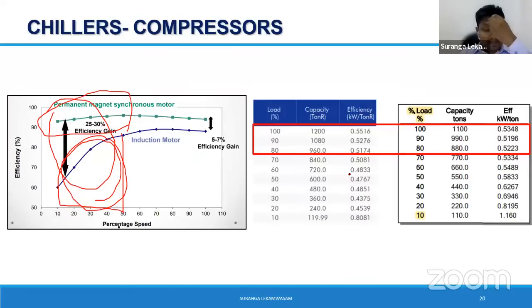Again, I have extracted a comparison which I was involved with. This is a 1,000-ton chiller. The left one is a magnetic bearing chiller. The right one is a conventional bearing chiller. Both are centrifugal chillers. At 100% load, the magnetic bearing chiller gives 0.55 kilowatt per ton, whereas my conventional chiller is better in efficiency at 0.53. At 90%, my conventional chiller is still better. But when you go down to 80, 70, let's say 60%, it's 0.48 versus 0.54. Now my magnetic bearing chiller is much better.